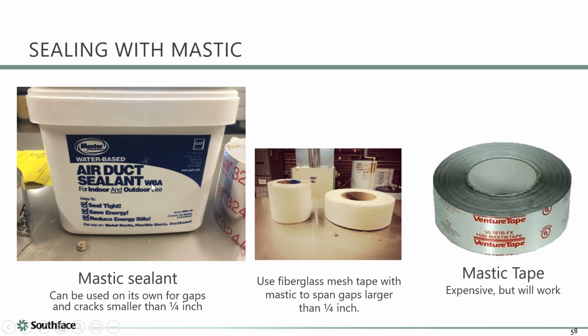I like the kind that has little fibers in it, but if it's a big gap, you can also use the same kind of scrim tape you would use for a drywall mud joint. They also make a mastic tape, which is a thick tape. It's very expensive, but you'll know it's thick. And then there's regular UL 181 tape, which is also permitted, but we're going to suggest don't use it. In Georgia, it's not allowed to be used as a sealant. That was something we amended our code to do.